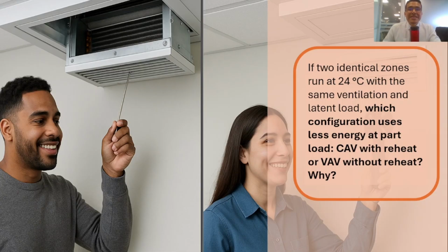In CAV, the coil exit temperature is held roughly constant and airflow is constant, so the coil load tends to stay high and reheat increases as the sensible load drops. In VAV, as you can remember, the coil exit stays low for dehumidification, but airflow falls with the load, lowering coil and fan energy until the minimum flow threshold.